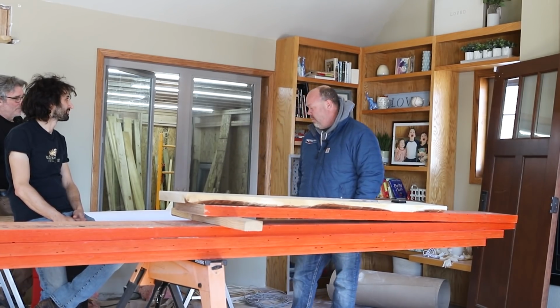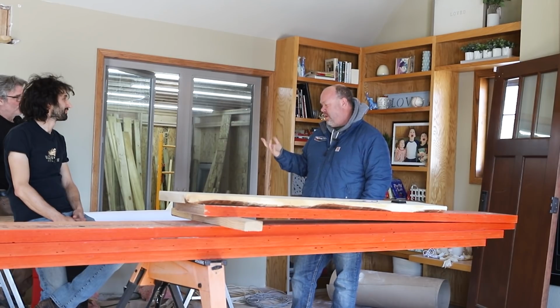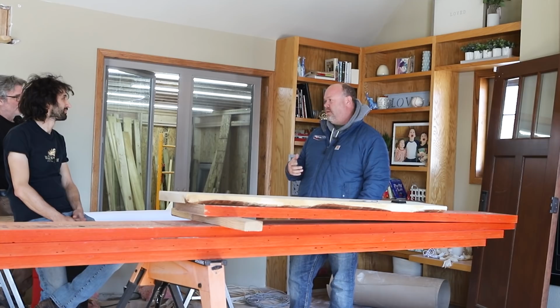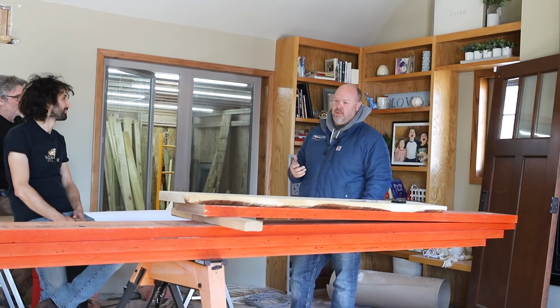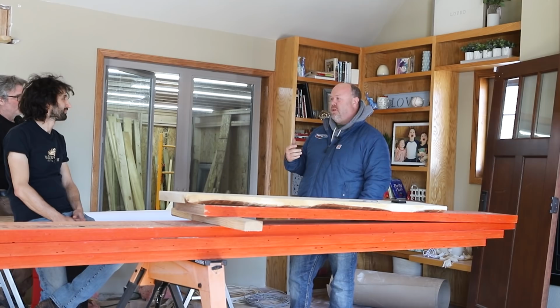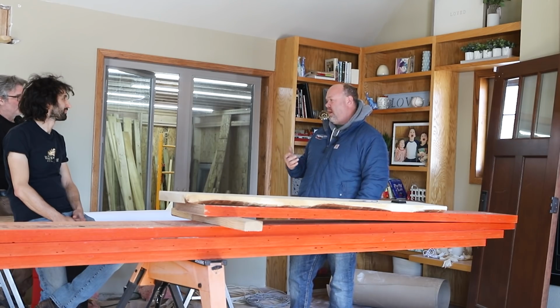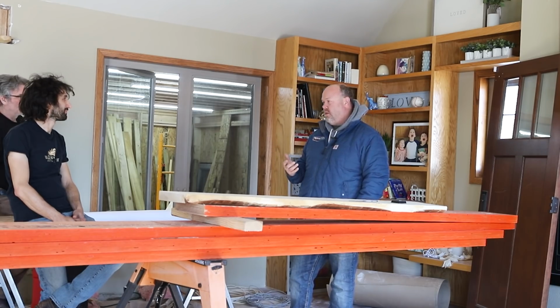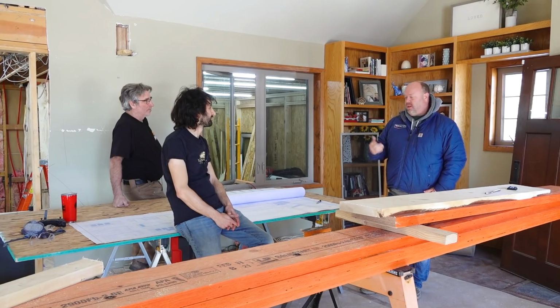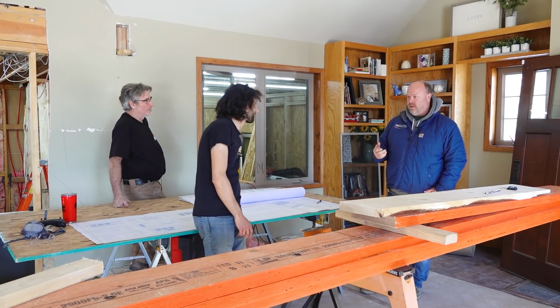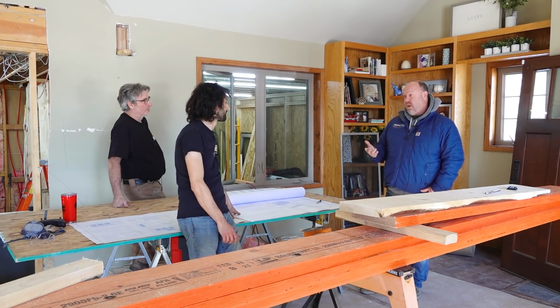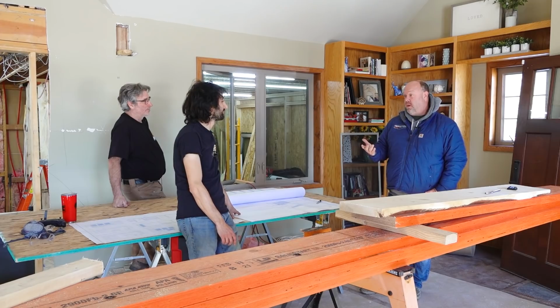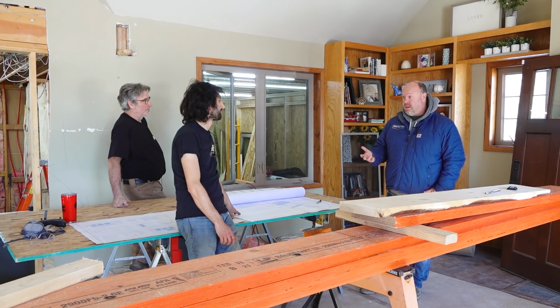With that, there's a book called Manual J. Engineers years ago figured out how to measure R-value and a multiplier for the heat loss or gain. We put in your square footage, exterior walls, what's below grade, what's above grade, and the building materials used. So you could have two houses that look identical, in the same market and region, and come up with a different heat loss based on materials used.